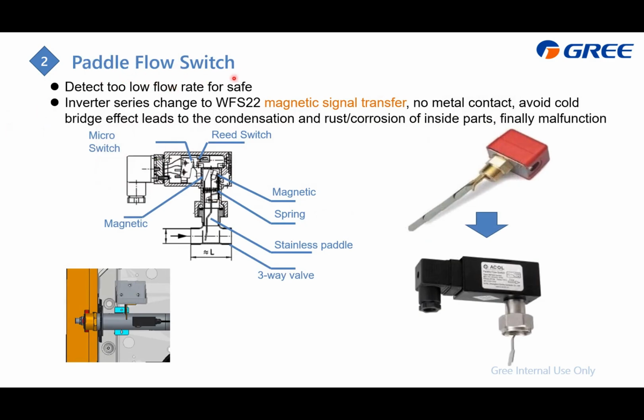Paddle flow switch. The purpose of this one is just to detect the water flow rate to ensure the water flow rate is enough. In our latest one, we adopt the WFS22, the magnetic signal transfer, to replace this one. The purpose is to avoid condensing water accumulating here, which causes rust and corrosion inside and finally may lead to malfunction. We changed it to this one.